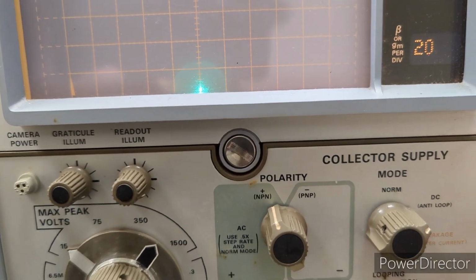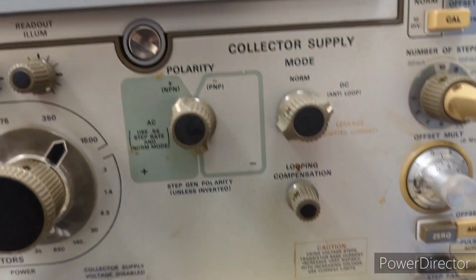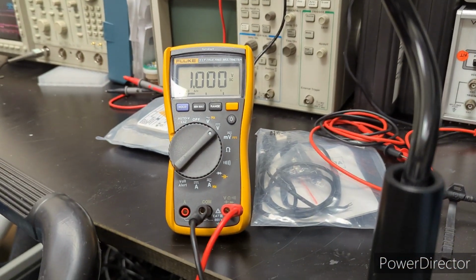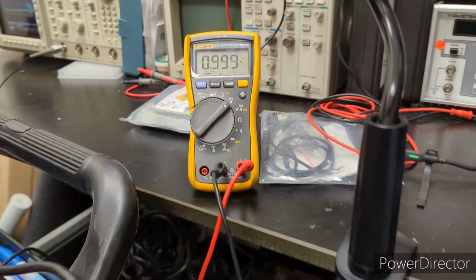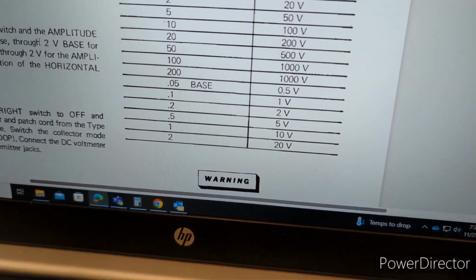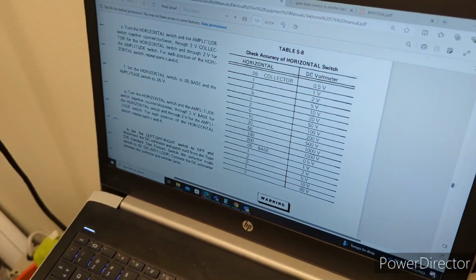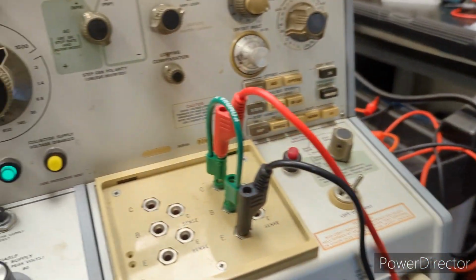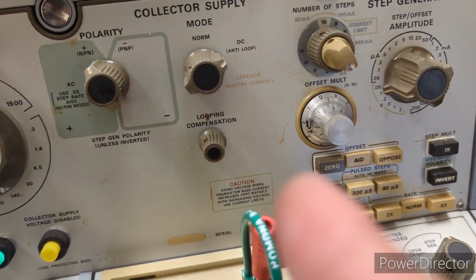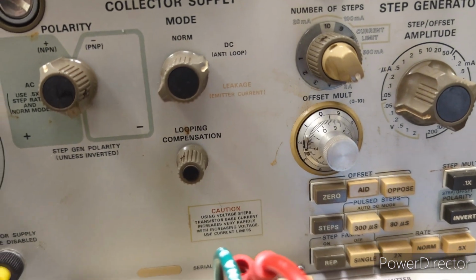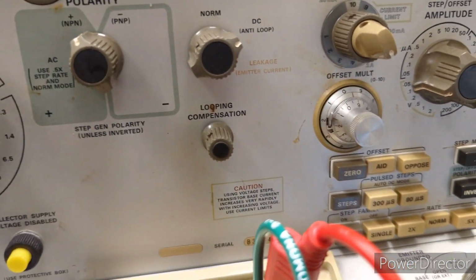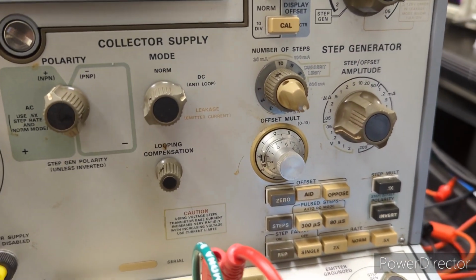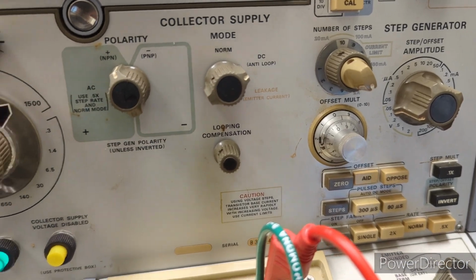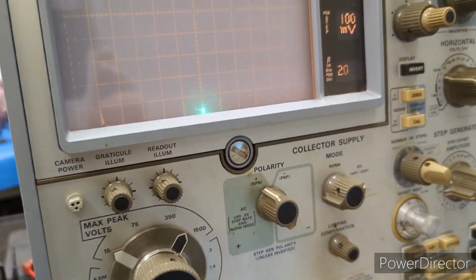So here it's not really requiring us to do much adjustment at all. Again, you're using the offset multiplier switch to make that adjustment, and you can see it's bang on at 1 volt, and that is what we should be getting. So for 0.1 volts for the base, 1 volt. Everything's looking good as far as accuracy for the horizontal switch, and the fact that we're able to do it with the offset multiplier switch, which wasn't working before, is because that's adding or subtracting voltage or current from the step generator output. So there you go.